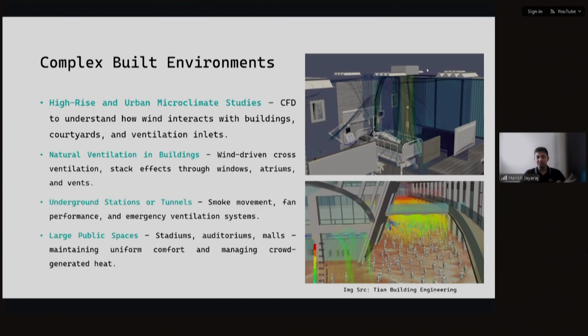And there is underground stations. This is very popular in Indian scenarios because we have a lot of subways, metros, and parkings in buildings. So smoke movement becomes very necessary. If there's unfortunately a fire, how fast can it be extinguished, and how fast can the smoke move? Fire extinguishers are everywhere, but how fast can the smoke move, since smoke is toxic, even for firefighters? So how fast can you move it, how do you place the ventilation system, and how do you contain the fire?